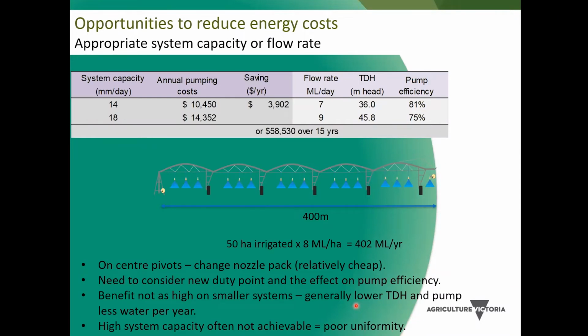In actual fact, on a lot of systems that we go and look at, we find where they're designed with a very high system capacity, the first thing we do is measure pressure at the end of it, and we'll find that pressure's low. They're actually not capable of even pushing the water through that system. So by reducing the system capacity, we're reducing operating costs and improving the uniformity of the system. So it's a win-win.